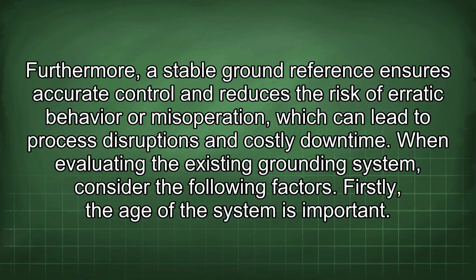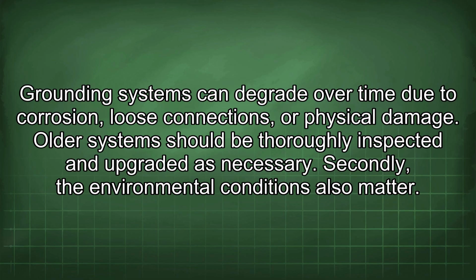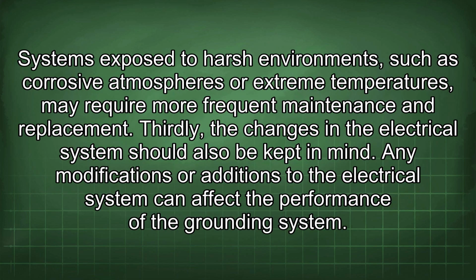When evaluating the existing grounding system, consider the following factors. Firstly, the age of the system is important. Grounding systems can degrade over time due to corrosion, loose connections, or physical damage. Older systems should be thoroughly inspected and upgraded as necessary. Secondly, the environmental conditions also matter. Systems exposed to harsh environments such as corrosive atmospheres or extreme temperatures may require more frequent maintenance and replacement.